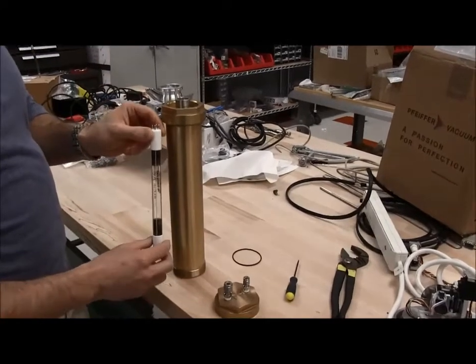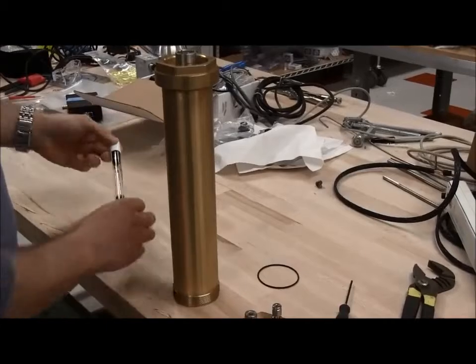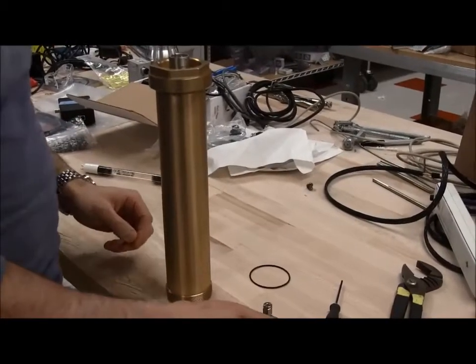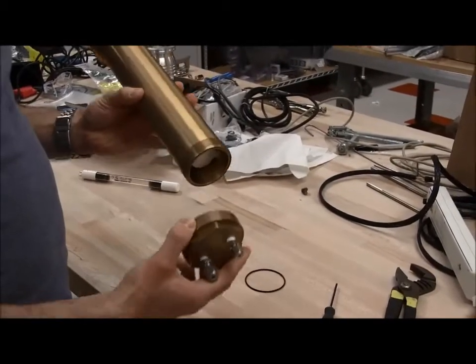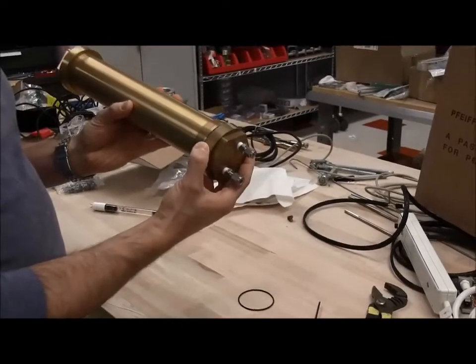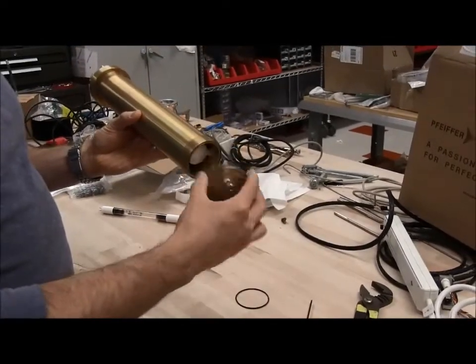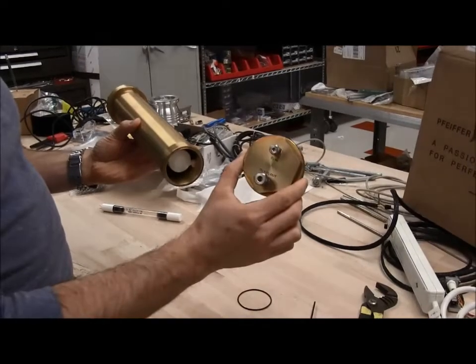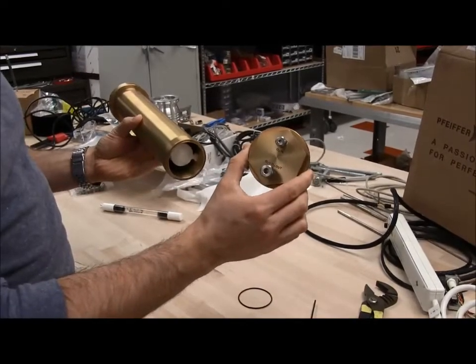What I'm going to demonstrate won't, but so it sits on the inside here, and so we need to get access to it in order to replace it. The ozone chamber will be sitting in a mounting bracket, you'll want to unscrew the bottom bracket that has the oxygen in, oxygen plus ozone out connections.